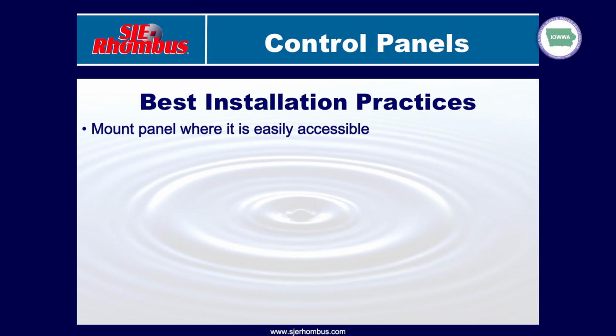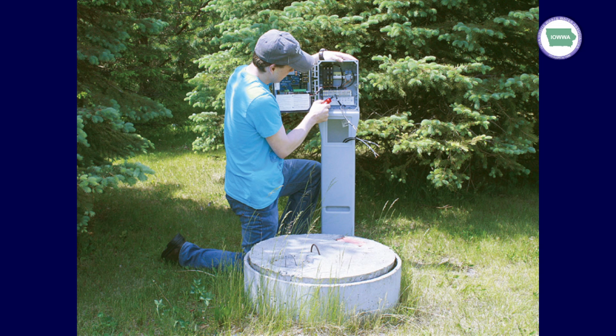And I never cease to be amazed at some of the installations that we come across. The first point we want to say is put the panel in an area that it's easily accessible, easy to do service work on it. And this picture here shows, you're going to mount the panel about 3-4 feet up off the ground in an area where you can actually get to it.